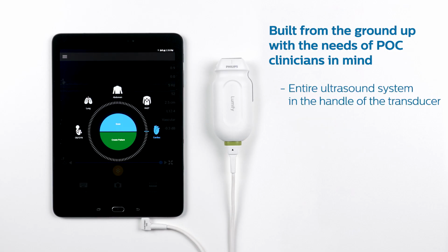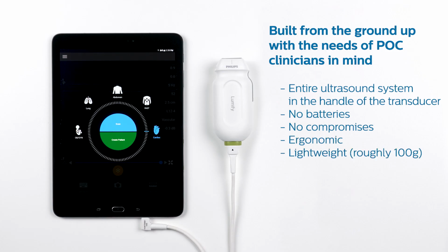First, we put the entire ultrasound machine in the handle of the transducer, and we were able to do this without loading up the transducer with batteries and without introducing the typical compromises that are common in other handheld systems today. This means the transducers are ergonomic, lightweight, around 100 grams, and they are at low risk of overheating. In other words, you can take them wherever you go, and they'll fit comfortably in your pocket.